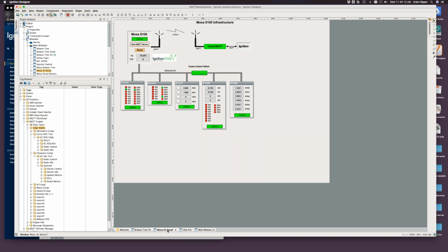One of the things, as Kurt said, is that we have a Moxa 8100 running Ignition Edge connected over a Verizon cellular network. Note here that we've got that Ignition Edge polling 5 Modbus TCP devices, and we've got the digital outputs on those devices tied back to the digital inputs.